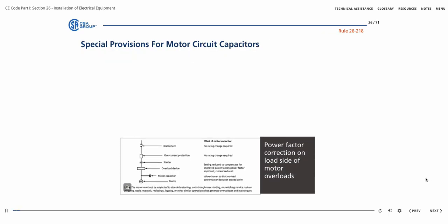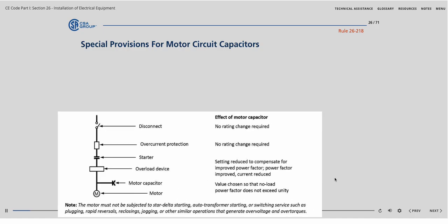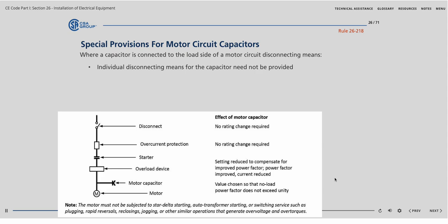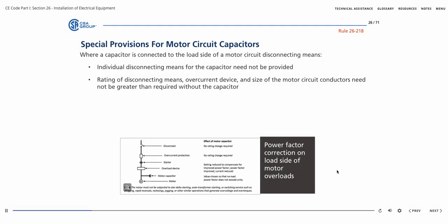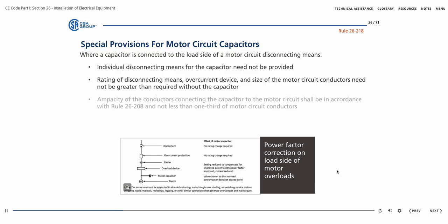There are special provisions that need to be followed when a capacitor is provided for an individual motor according to Rule 26-218, where a capacitor is connected to the load side of a motor circuit disconnecting means. Individual disconnecting means for the capacitor need not be provided. The rating of the disconnecting means, the overcurrent device, and the size of the motor circuit conductors need not be greater than would be required without the capacitor. And the ampacity of the conductors connecting the capacitor to the motor circuit shall be in accordance with Rule 26-208 and shall not be less than 1/3 that of the motor circuit conductors.